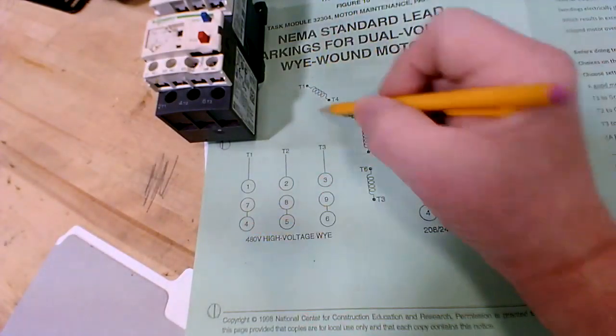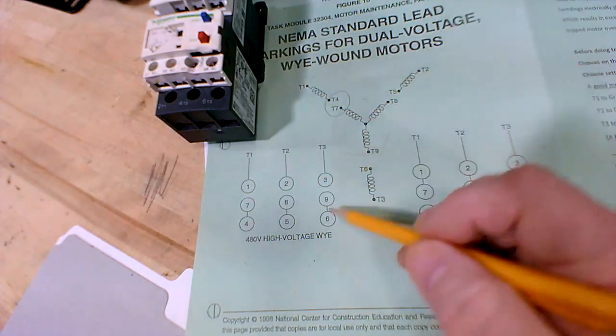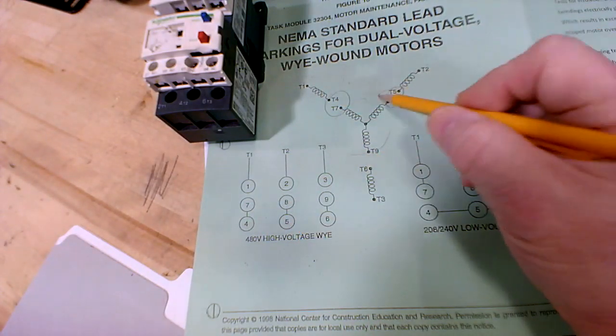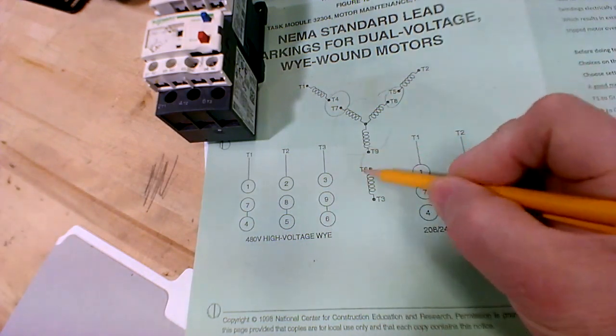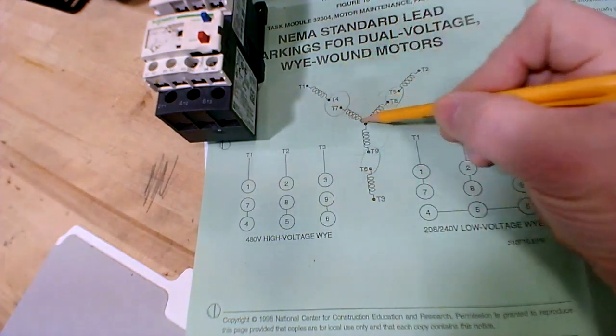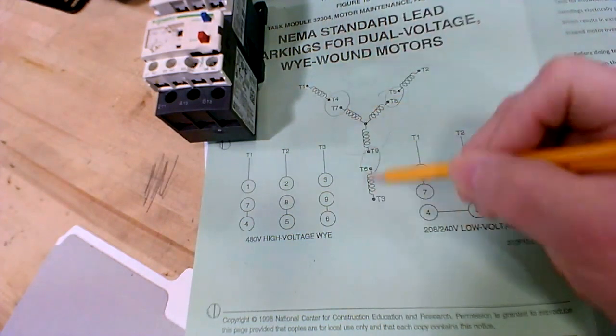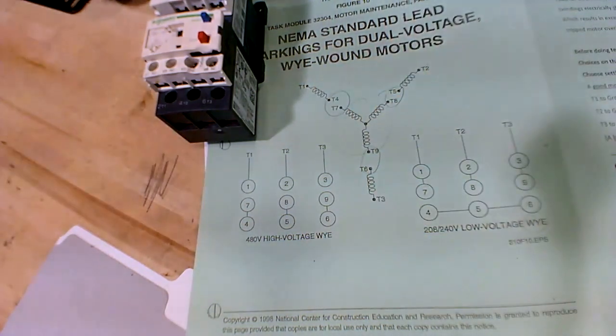You put a wire nut around 4 and 7, a wire nut here. You put a wire nut on 5 and 8. You put a wire nut on 6 and 9. And now this is considered to be series. These are all in series, not parallel.